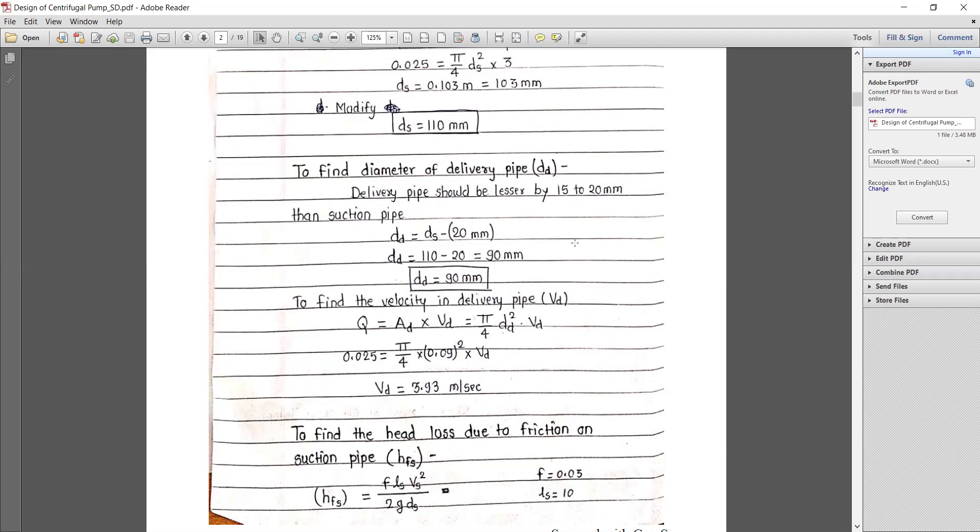The delivery pipe diameter dd = ds − 20 mm = 110 − 20 = 90 mm. Now we find the velocity in the delivery pipe. Using Q = area of delivery pipe × velocity of delivery pipe, we calculate the velocity of the delivery pipe as 3.93 m/s. As expected, the delivery velocity is greater than the suction velocity.